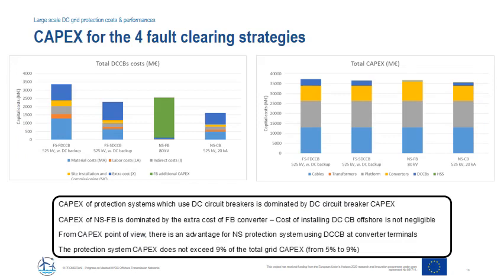The figure on the left presents the total cost of the protection system for the four considered strategies. For the non-selective protection strategies using full bridge converters, the additional cost of the converters with regard to a half bridge converter cost, here depicted in green, is added as a protection component cost. The figure on the right gives the contribution of the protection system costs to the total DC grid costs, including transformers, converters, and cables. The capex of protection systems which use DC circuit breakers is dominated by the DC circuit breaker capex, including breaking devices, reactors, and surge arrestor.